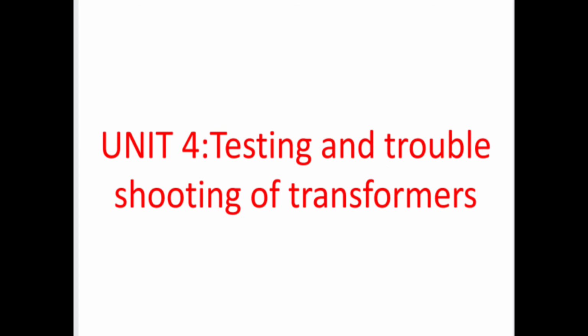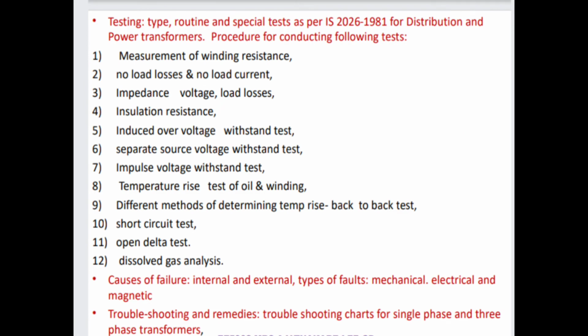So, now we start. First of all, testing. Types of testing: first is routine and special test. As per distribution and power transformers, the procedure for conducting the following tests. First is measurement of winding resistance. Second is no load losses and no load current. Third is impedance voltage and load losses. Fourth is insulation resistance. Fifth is induced over voltage withstand test.